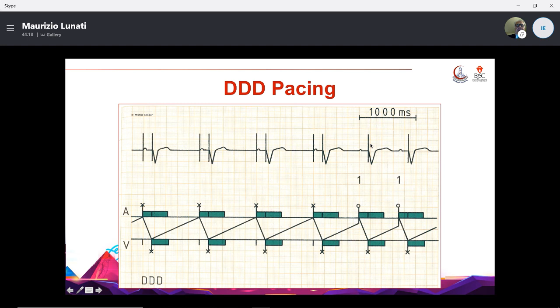What are the refractory periods? We should know that there are two extremely important refractory periods in the timing cycle of a device. We have an absolute refractory period, also known as blanking, which takes place in the initial portion of the refractory period. Every signal which appears in this time will not be detected. What does this mean? That in this period of time, the sensing channel is not active.